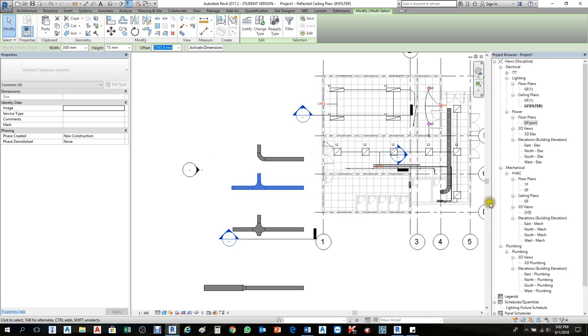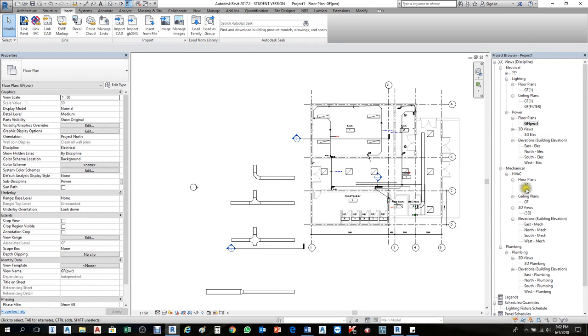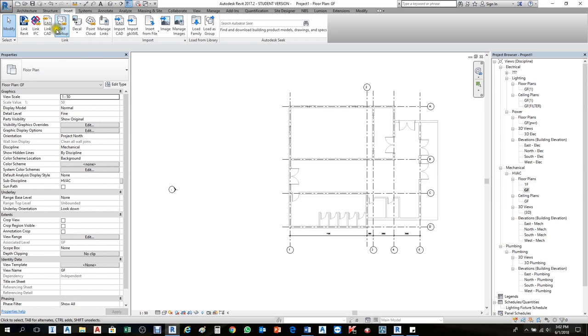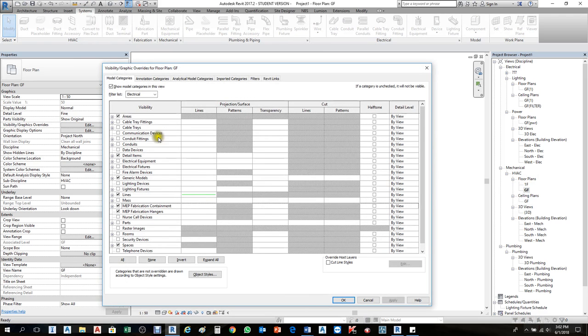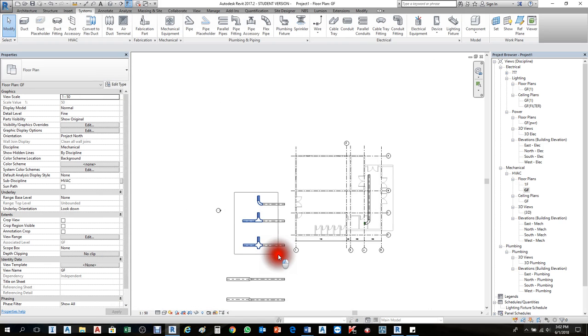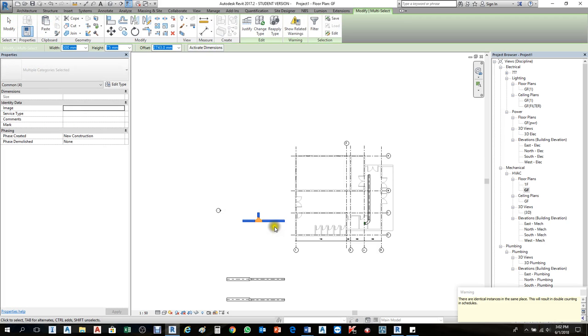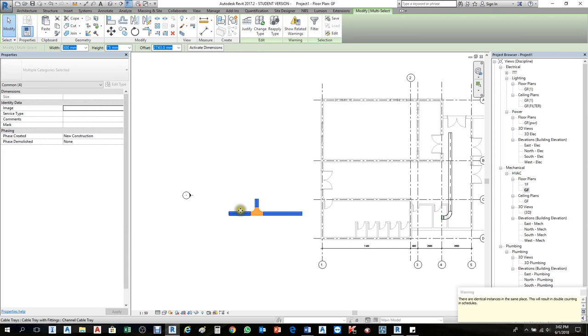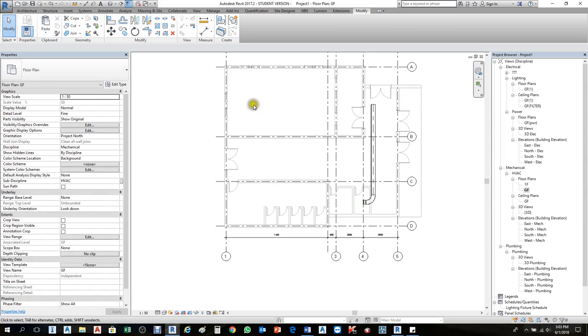For example, if you have cable trays in a Lighting model and want to paste them into a Ground Floor Power model, select those cable trays and use Copy to Clipboard. Navigate to the target view — for example HVAC — and before pasting, make sure Cable Tray and Cable Tray Fitting are visible in that view. Then use Modify, Paste, Align to Current View. If a warning appears it may be because cable trays already exist in that area for a different system.